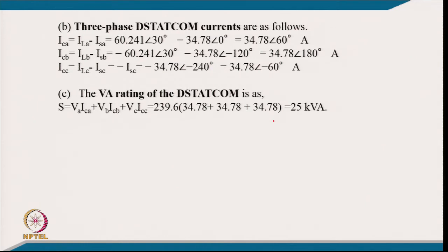So, this example gives you a typical example of load balancing, as well as unity power factor on the supply side, in spite of it being a single phase load connected across line to line, which is a very common load, like maybe a traction, maybe furnaces. Plenty of loads of this nature, of quite high rating, can probably be designed in the same manner, that is, STATCOM for those applications.